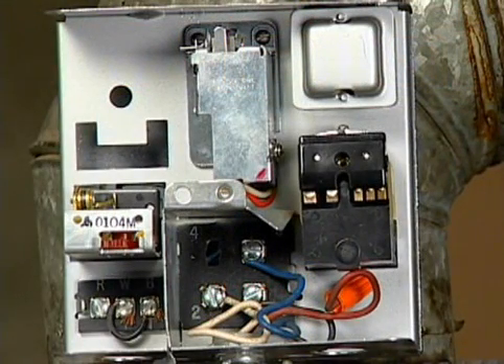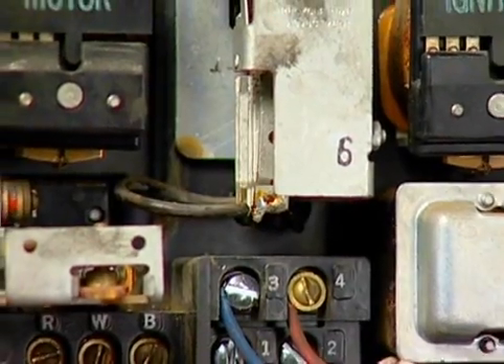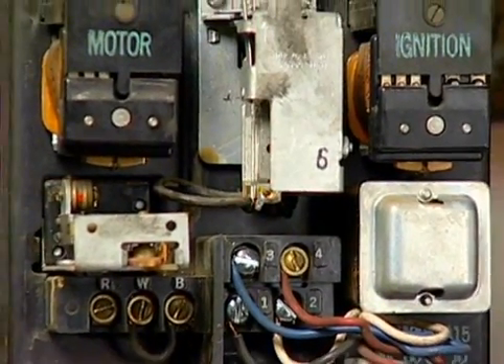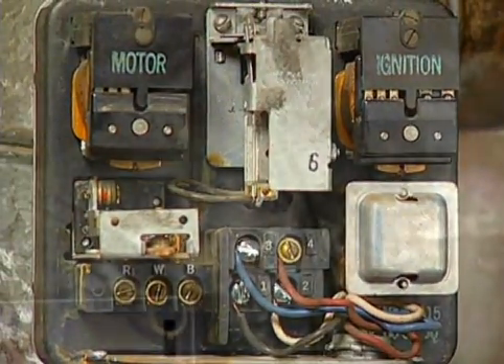Some of the older designs provided intermittent duty ignition. Again, this is the ignition method in which the spark is present for the entire time the burner is firing. And there are older interrupted duty ignition primary controls where the spark comes on only to light the flame.